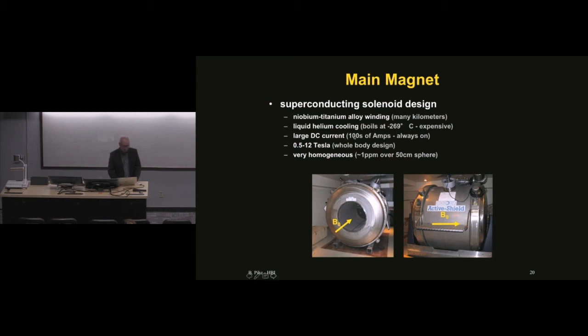At that temperature, the wire becomes superconducting, meaning the resistance vanishes to exactly zero. Large DC currents are injected, on the scale of hundreds and hundreds of amperes, flowing nonstop in those coils without a power source. You get the current going and remove the source, and it flows indefinitely because there's zero resistance. So these superconducting magnets have very high magnetic fields.